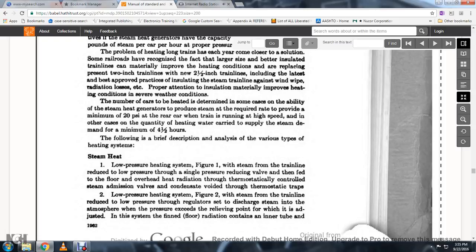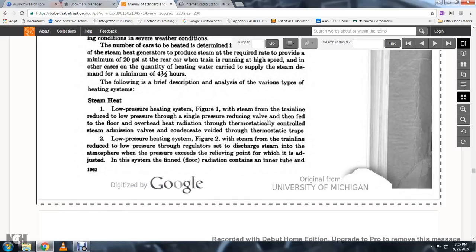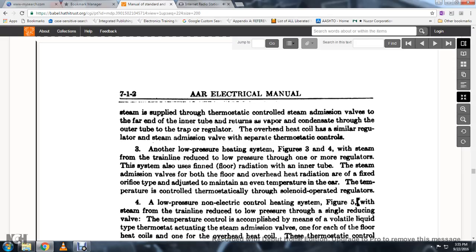Low pressure heating system, Figure 2: the train line steam is reduced to low pressure with a regulator set to discharge at near atmospheric pressure, adjusted with the system using floor radiation containing an inner tube, with steam supplied through thermostatically controlled steam admission valves through the far end of the inner tube. The condensate returns through the outer tube with a trap and regulator, with overhead heat similarly regulated with a separate steam admission valve and thermostatic control.